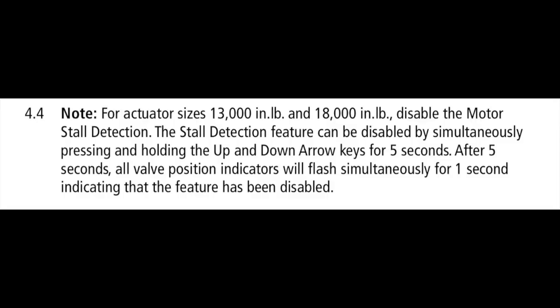For actuator sizes 13,000 inch-pounds and 18,000 inch-pounds, disable the motor stall detection. The stall detection feature can be disabled by simultaneously pressing and holding the up and down arrow keys for 5 seconds. After 5 seconds, all valve position indicators will flash simultaneously for 1 second, indicating that the feature has been disabled.